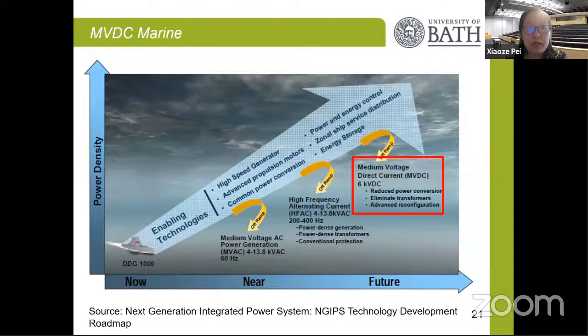And a second area is that medium voltage DC has been talked about a lot for transportation electrification. For example, the roadmap for future marine applications is starting to look into medium voltage DC up to 6 kilovolts, because, firstly, it reduces power conversion, and secondly, it doesn't need synchronization of different AC systems. And also it can provide very high power quality if there is a pulse load in the marine application.